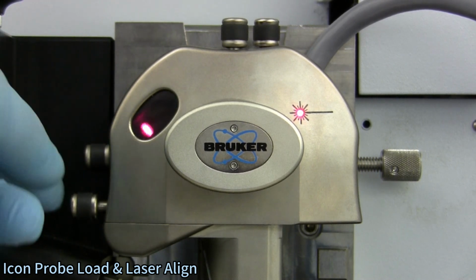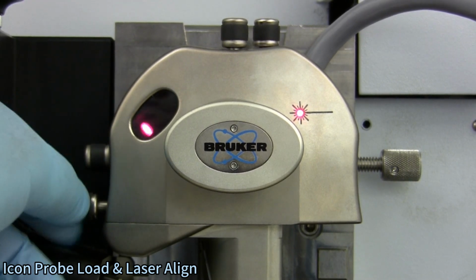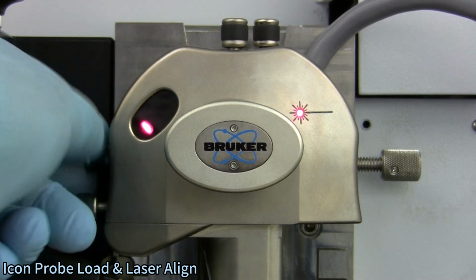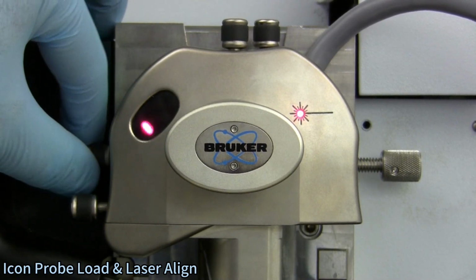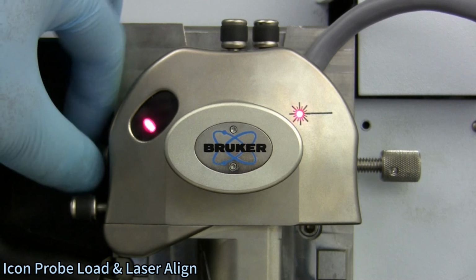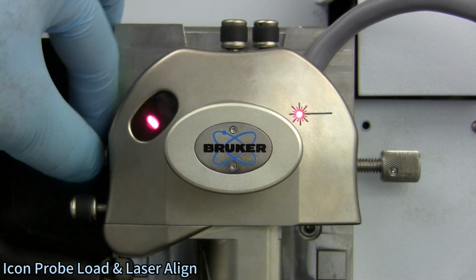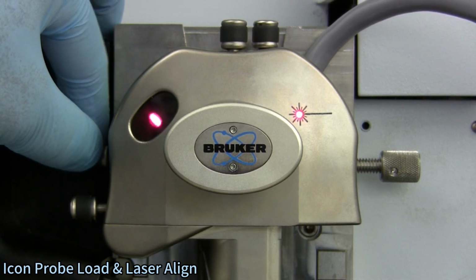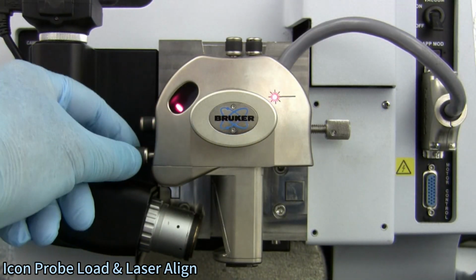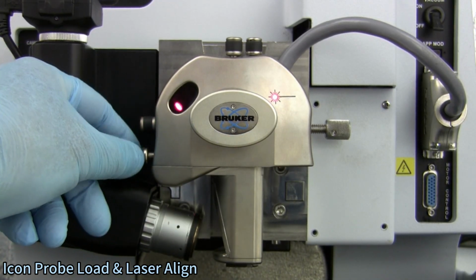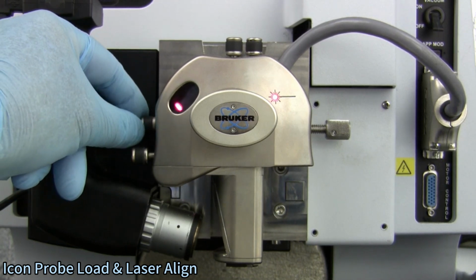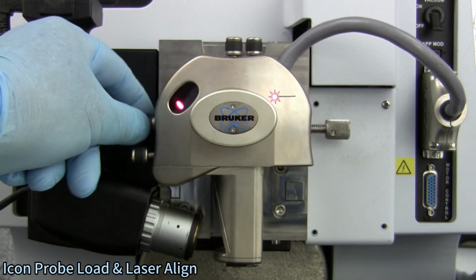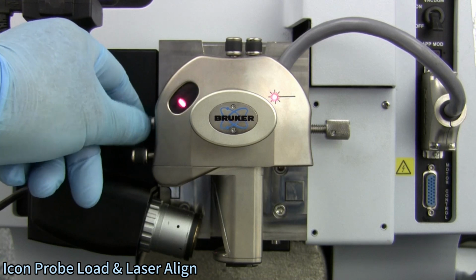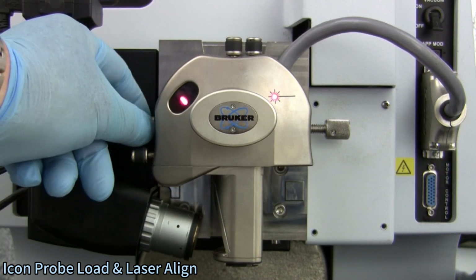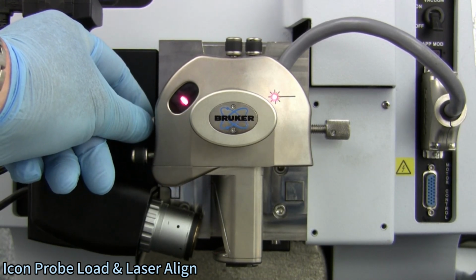Rotate the detector adjustment knobs to steer the reflected laser into the position-sensitive photodetector. The window on the left side of the head reveals the position of the reflected beam. Typically, the optimum position will be near the center of the window. Occasionally, the reflected beam may be too far off-center to show up in the window. It may be necessary to rotate the detector adjustment knobs all the way into their respective stopping positions and then rotate them back out one at a time until the spot reappears.